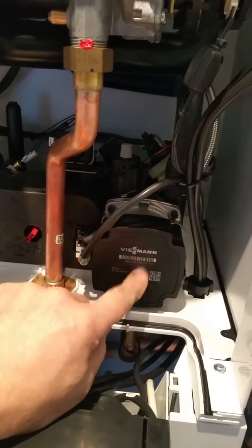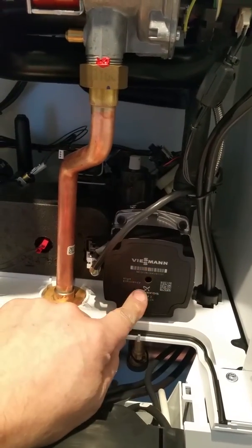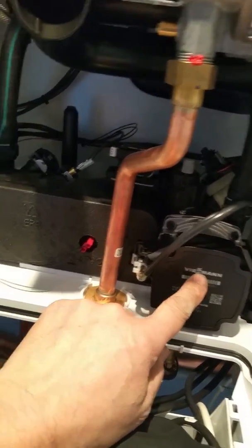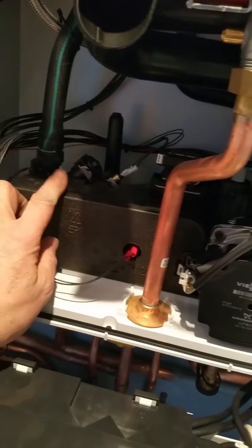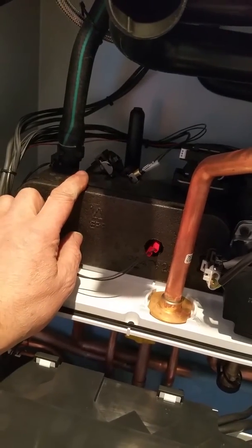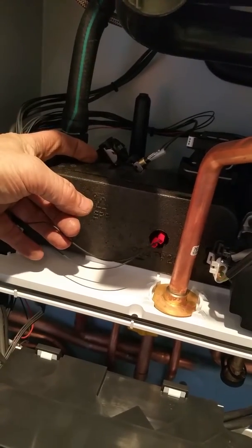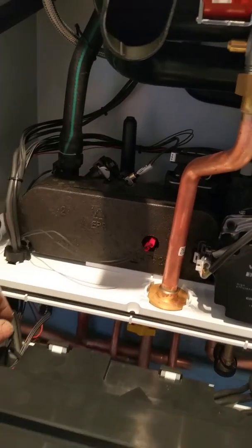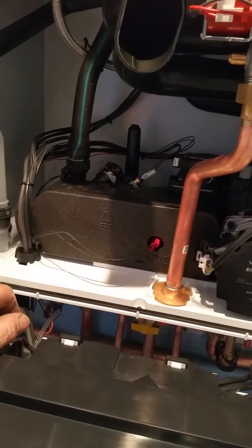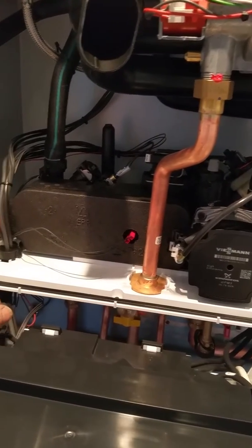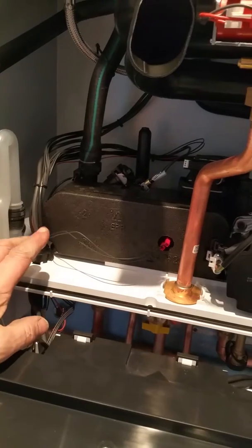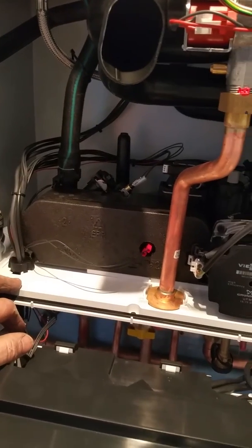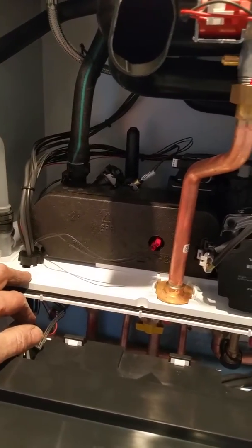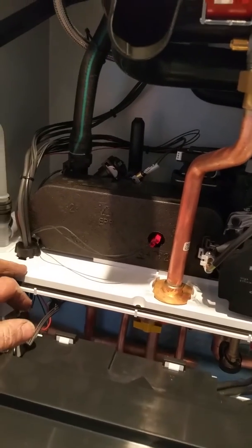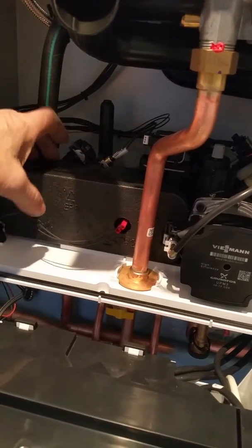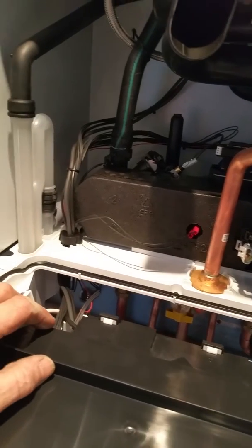One of the new pumps, which we know is a problem for all boilers, is going to be a constant nightmare on dirty systems. The plate heat exchanger I think is far too small. The beauty of a Viessmann 200 for years has been the big, beefy heat exchanger, which allowed for the fouling factor and gave much longer service between problems. This is going to be more problematic - we'll be coming out and cleaning plate heat exchangers on these like we do on all the other boilers. If we're lucky, they might sell an uprated plate heat exchanger for this and give us a bigger one.